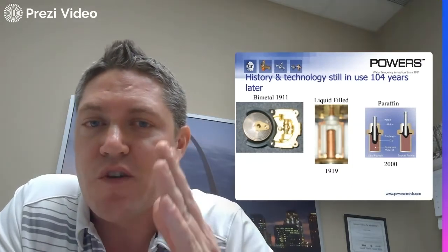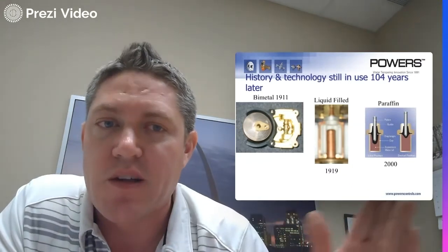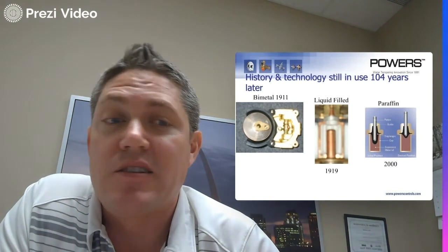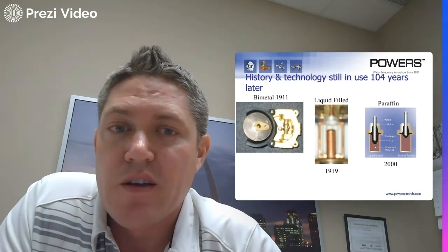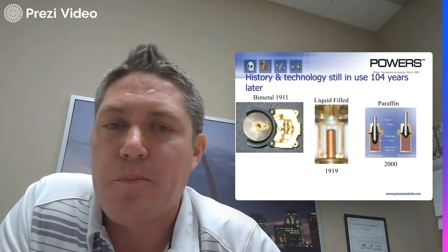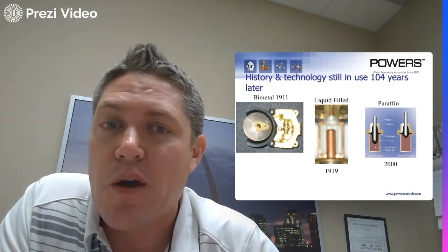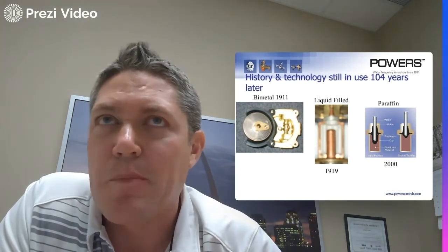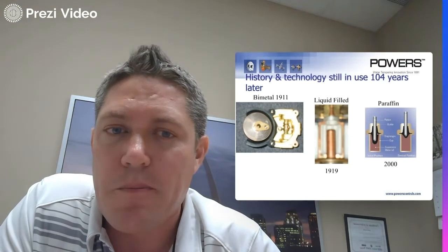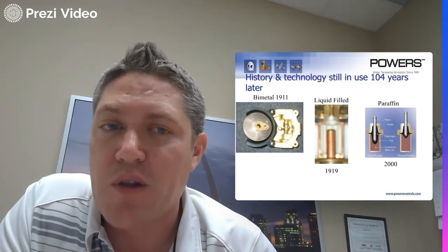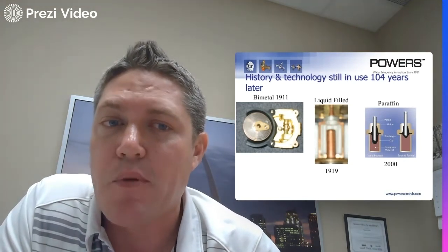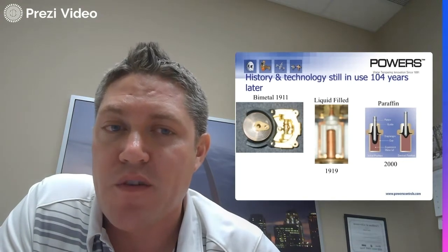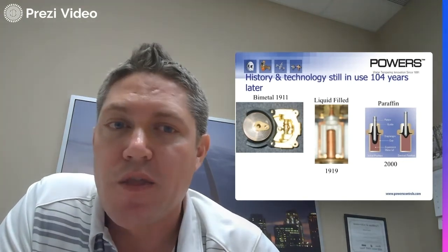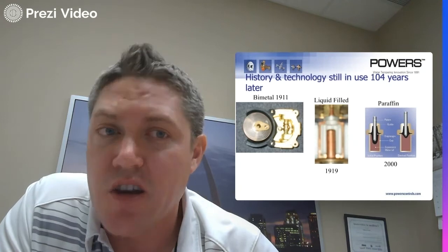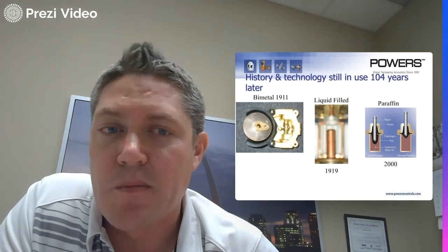And so the reason for going from bimetal to liquid to paraffin is basically tighter temperature control. Where you were roughly plus or minus 15 degrees from set point with a bimetal, then you were plus or minus 10 degrees from set point with a liquid-filled, and then plus or minus 7 degrees from set point with your paraffin-filled cartridge. And that's where thermostatic technology currently sits for thermostatic mixing valves.